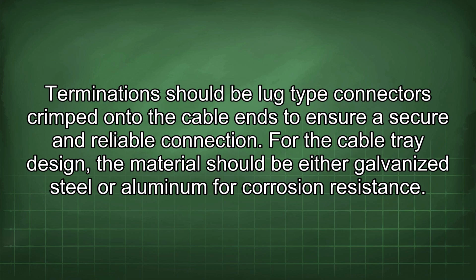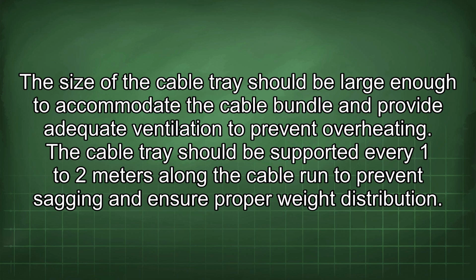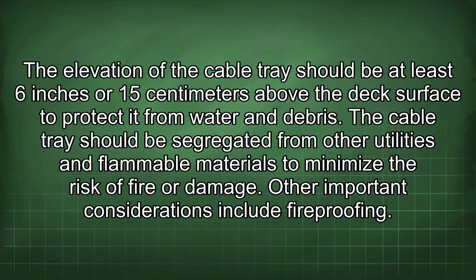For the cable tray design, the material should be either galvanized steel or aluminum for corrosion resistance. The size of the cable tray should be large enough to accommodate the cable bundle and provide adequate ventilation to prevent overheating. The cable tray should be supported every 1 to 2 meters along the cable run to prevent sagging and ensure proper weight distribution. The elevation of the cable tray should be at least 6 inches or 15 centimeters above the deck surface to protect it from water and debris. The cable tray should be segregated from other utilities and flammable materials to minimize the risk of fire or damage.